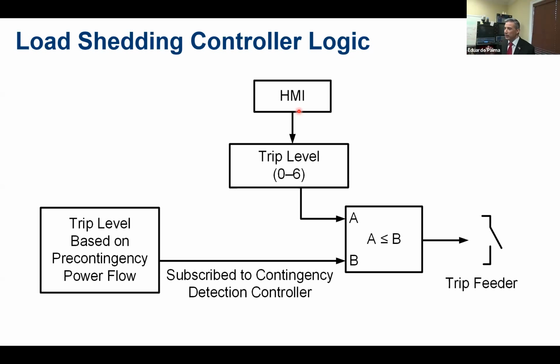It is very important to understand that a power system is constantly changing, and most of the time maintenance is being done. So if maintenance is being done, and we have to tell the logic that operates in milliseconds, some of these original thresholds or levels have to be modified by an operator in order for them to be able to do maintenance on some lines and still compensate through other variables. The HMI that we're about to see is how an operator physically goes to a keyboard and mouse and types in the information that needs to be compared in order to open the loads or a feeder.